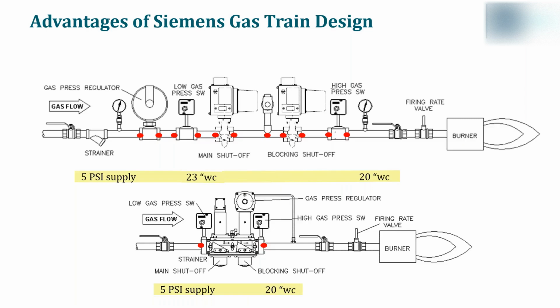Since we take the pressure drop of the second valve, we have the ability to reduce the size of the double gas valve to 1.5 inches. So the Siemens advantage allows us to maintain the same output, but with a smaller gas train. If you don't believe me, let's do an example.